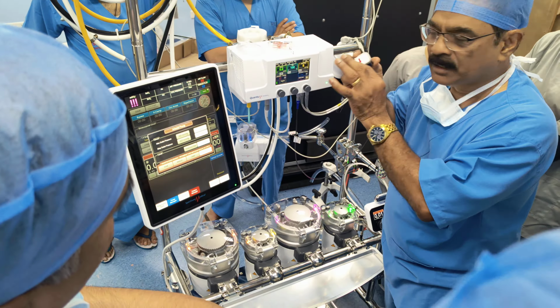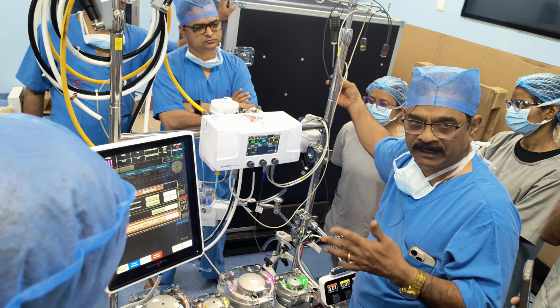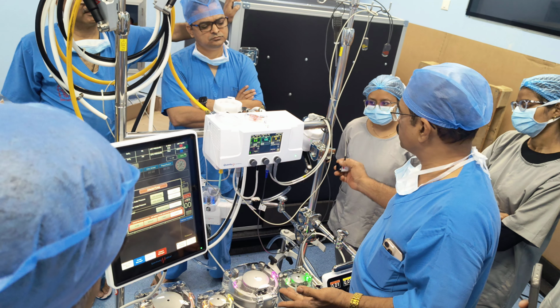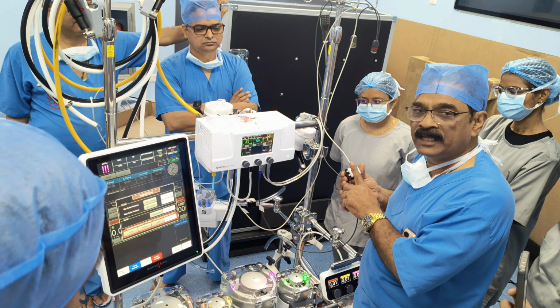This will sense the flow and give you, in liters per minute, the actual flow going to the cannula. So you normally place it beyond your shunt line, beyond your arterial filter. Okay? This, however, has a bubble activation for bubble sensing. So here you see there is a bubble flow. Now I have disabled it. I can put it on medium.